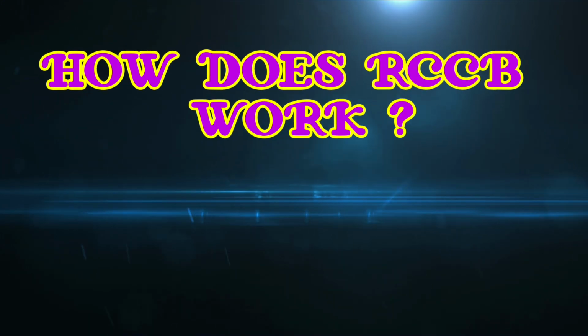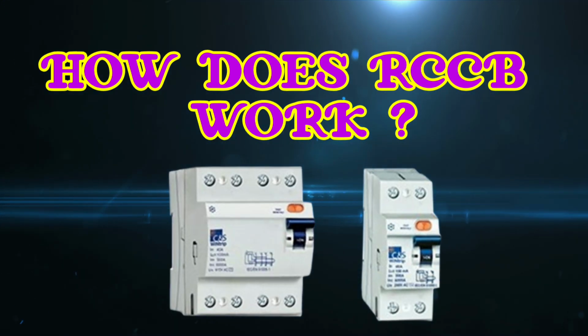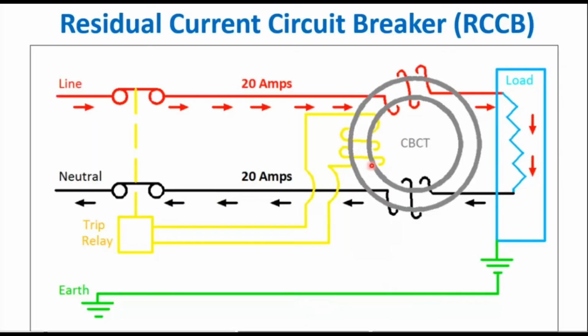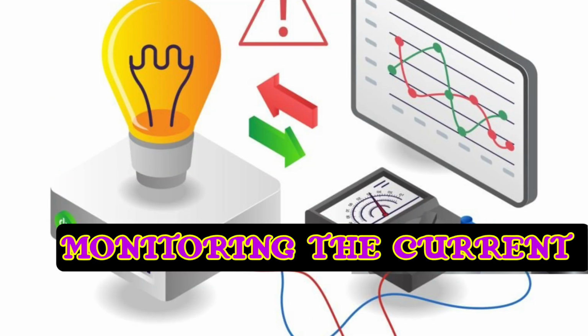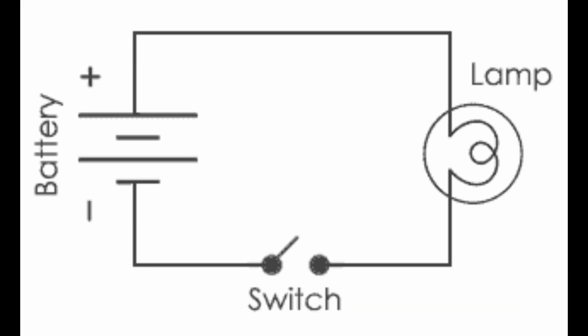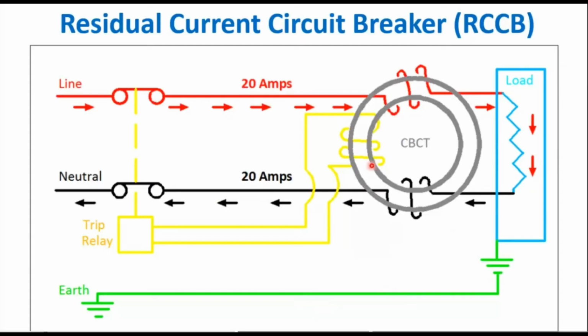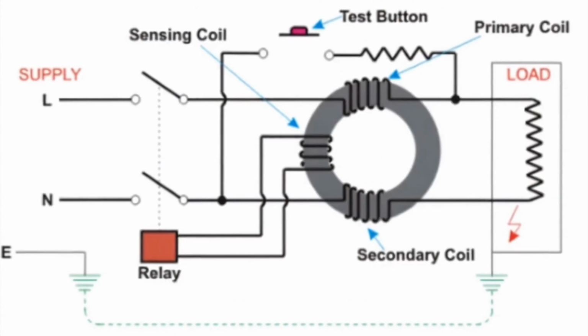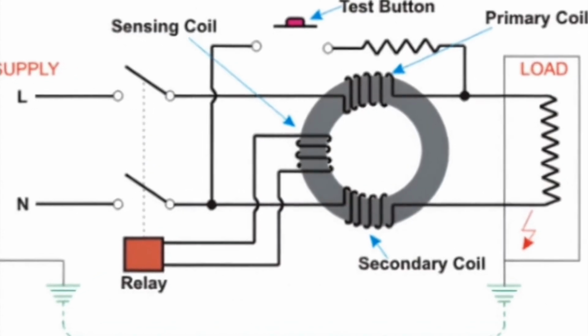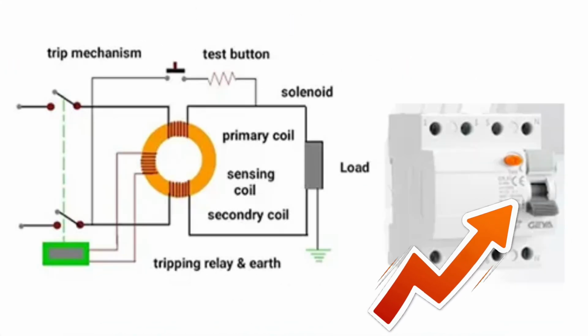Let's talk about how an RCCB works. RCCB continuously monitors the current flowing in the live and neutral wires. Under normal conditions, both currents are equal, but if there is a leakage, the RCCB detects the imbalance and trips the circuit. This happens within milliseconds, ensuring maximum protection.